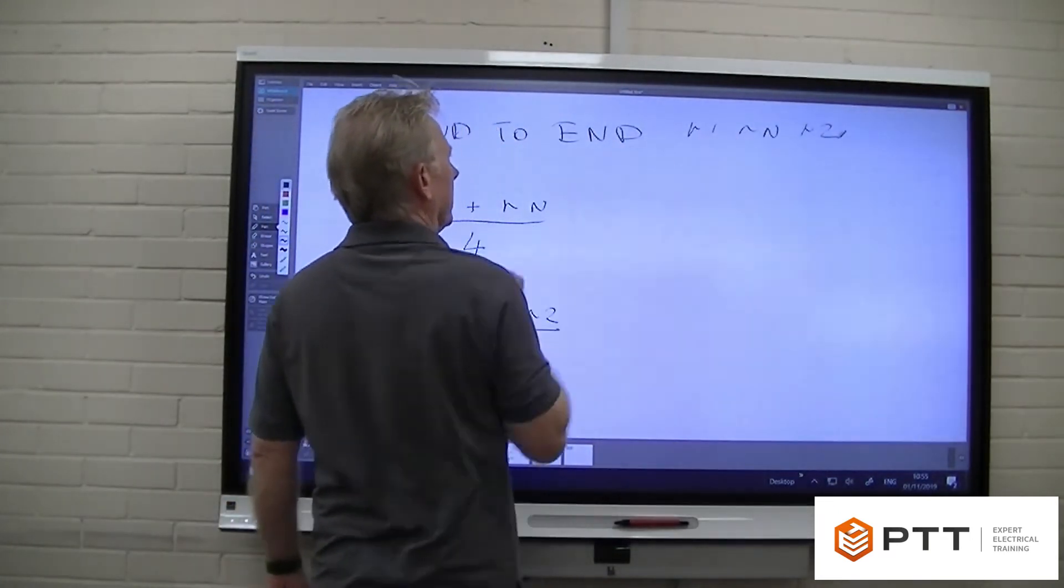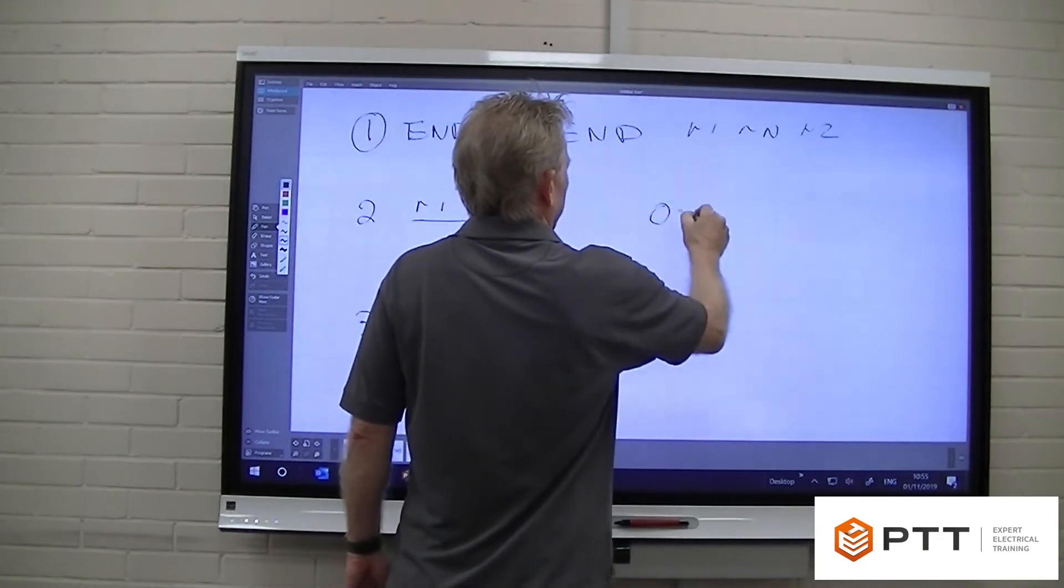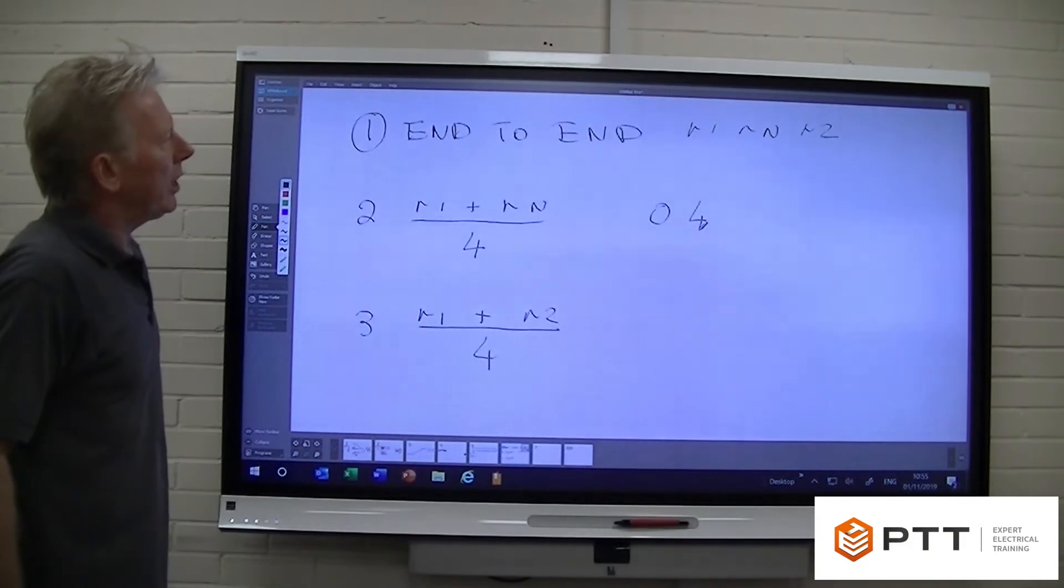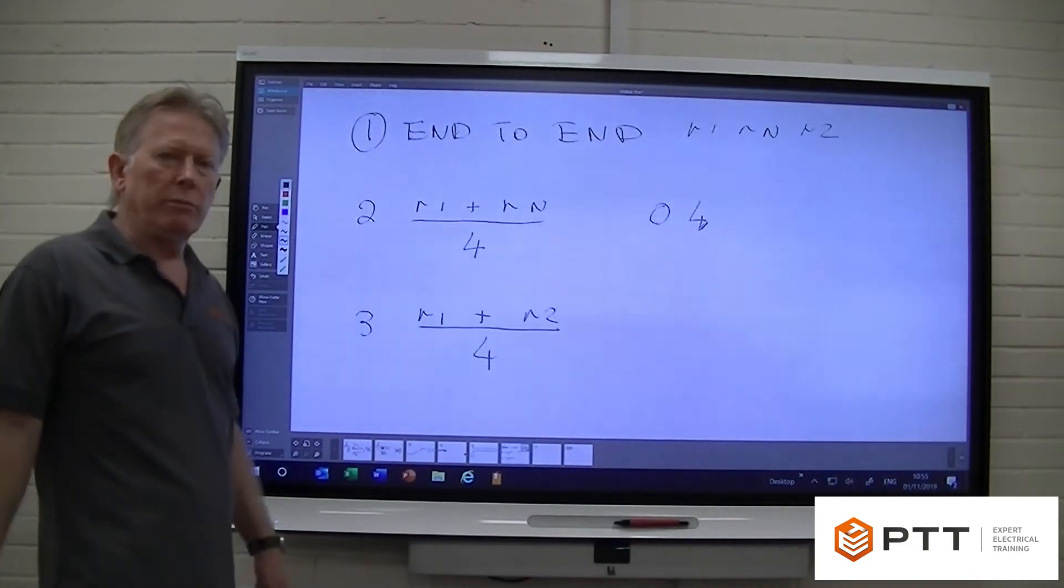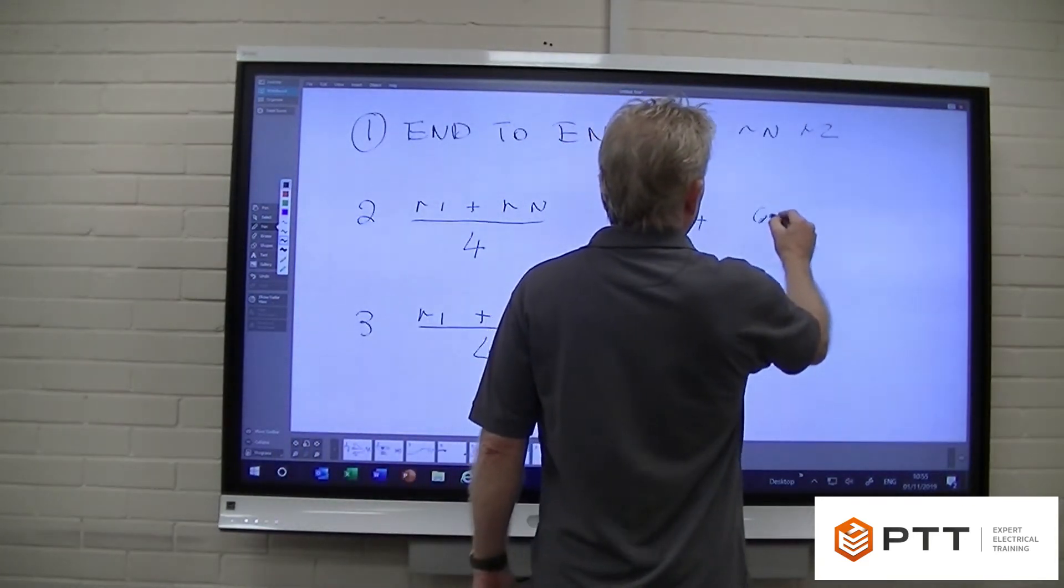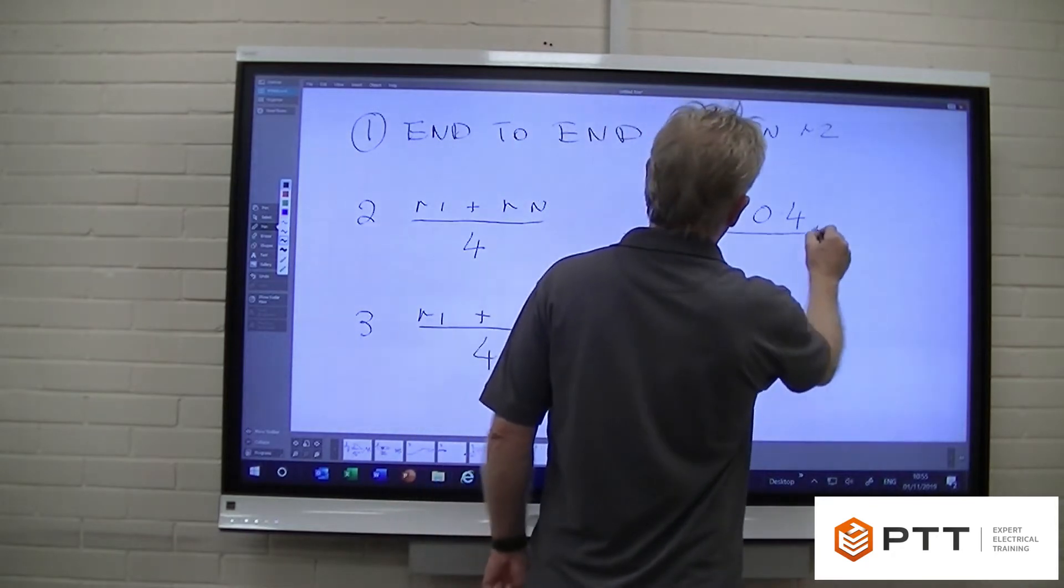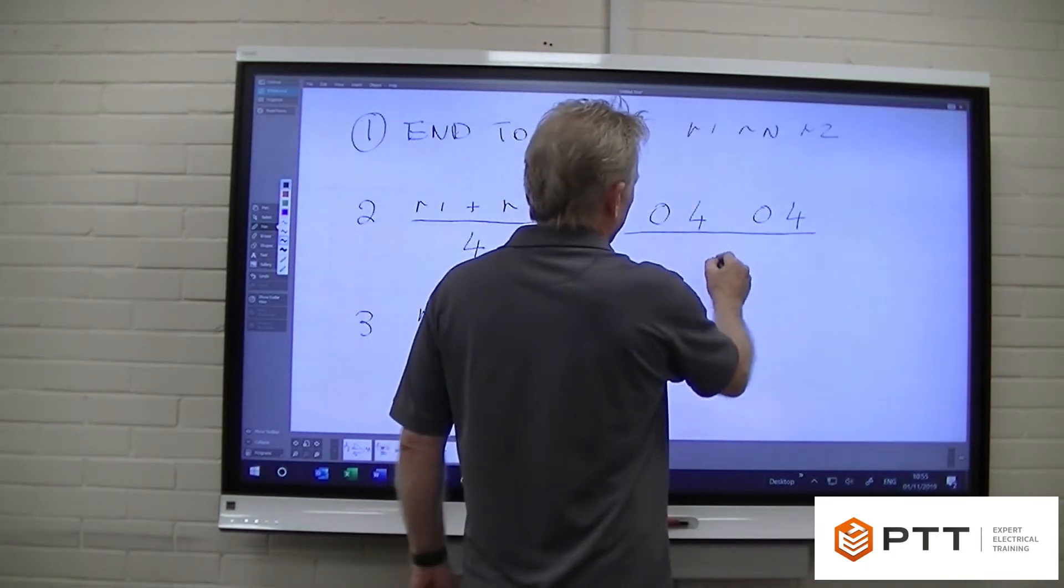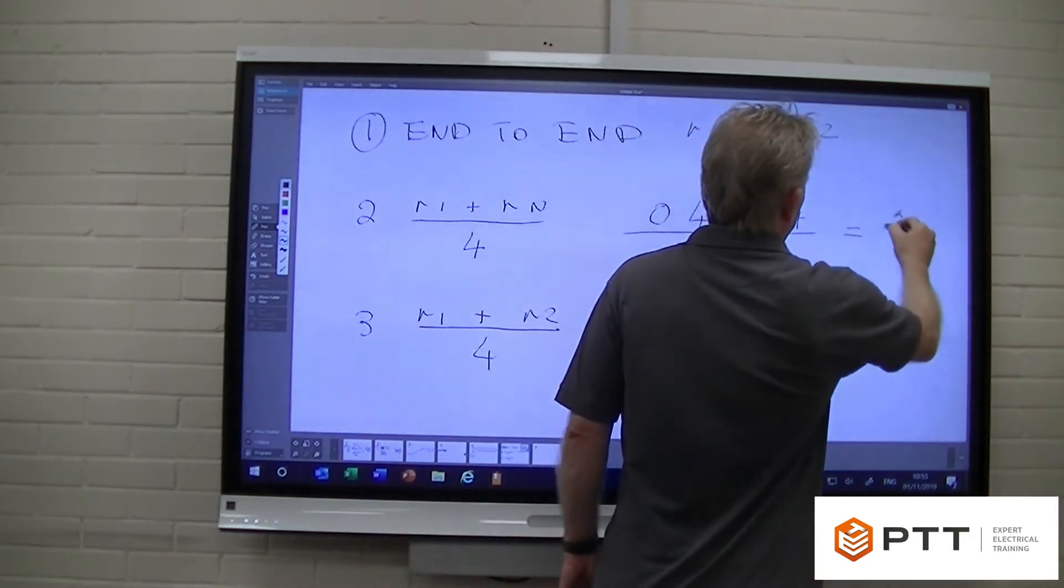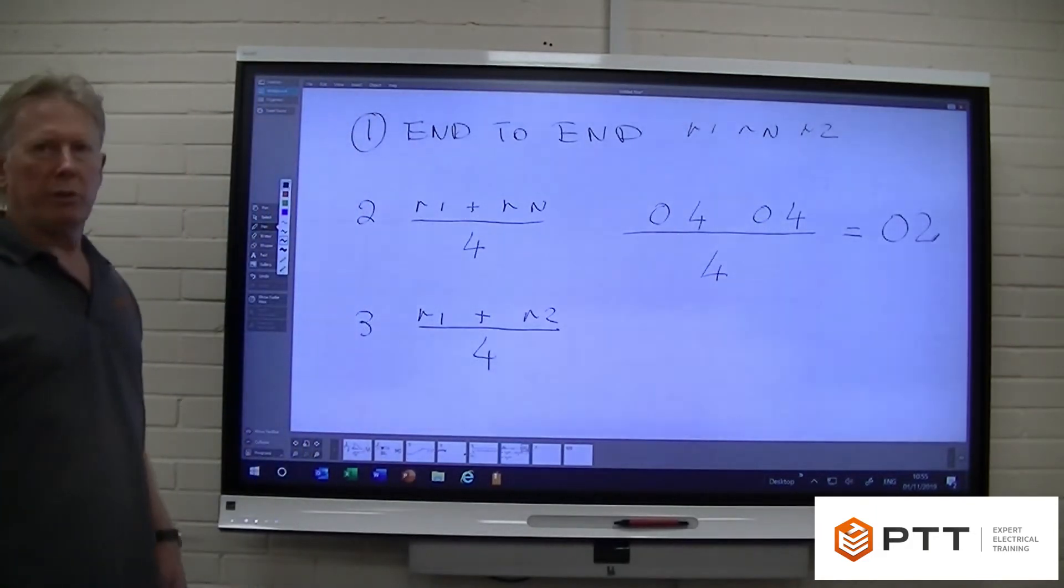So what I'm actually going to do is let's say that we measure r1 as 0.4 ohms for instance. Now rn is really the same cable going by the same route, so it should really be very much the same. Let's say that's 0.4. If we now divide that by four, that gives us 0.2 ohms. So when we do our cross connection, we should be able to measure 0.2 ohms at each socket.